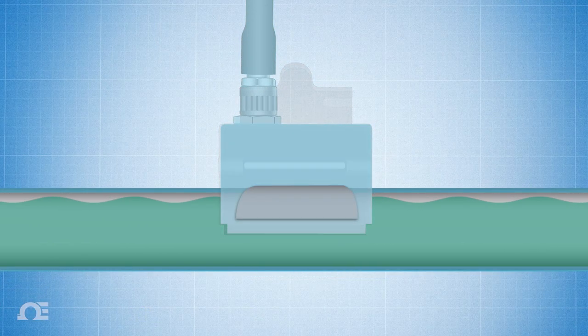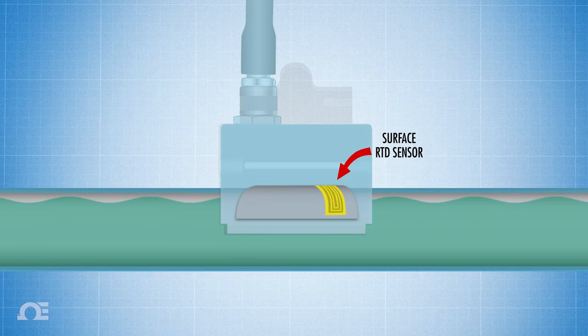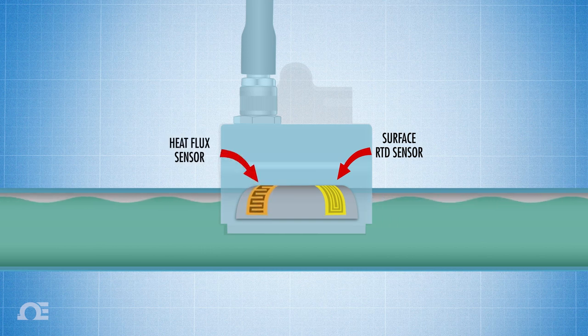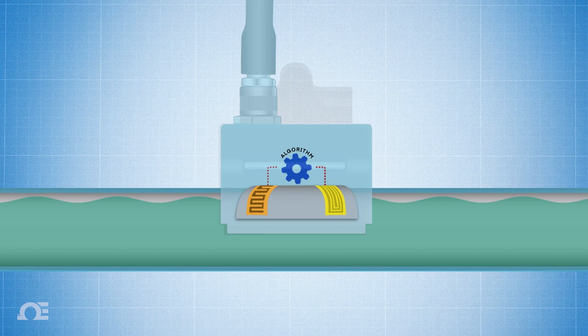The HANI sensor uses a carefully coupled surface RTD sensor in conjunction with a thin-film heat flux sensor and runs both data sets through a proprietary algorithm to calculate the temperature of the fluid inside the pipe or tank.